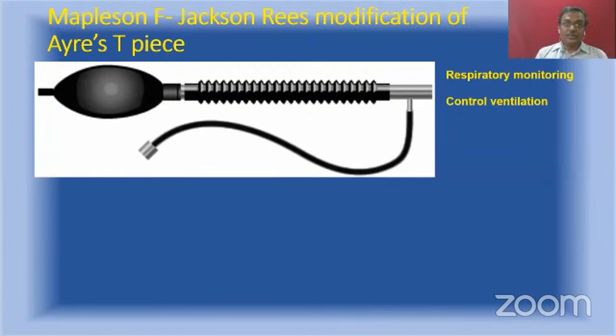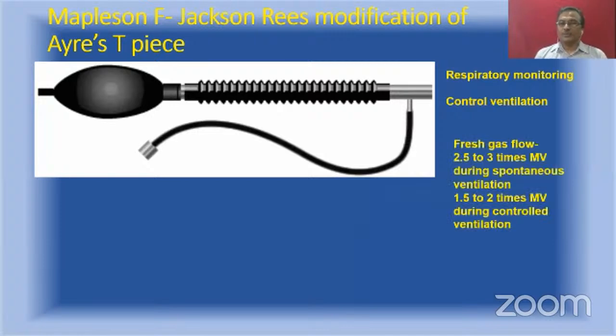With the T-piece, controlled ventilation was done with your thumb. You call it thumb ventilation. You have to intermittently occlude the expiratory limb, which will facilitate inspiration. Of course, there is a danger of barotrauma. If you keep the expiratory limb closed for a longer time, there's a chance of alveolar rupture and pneumothorax. But here, that problem is not there because there's a reservoir bag which will buffer the airway pressures inside the circuit. And fresh gas flow requirements are similar to those of a T-piece. With spontaneous breathing, it is about 2.5 to 3, and with controlled ventilation, it is 1.5 to 2 times.